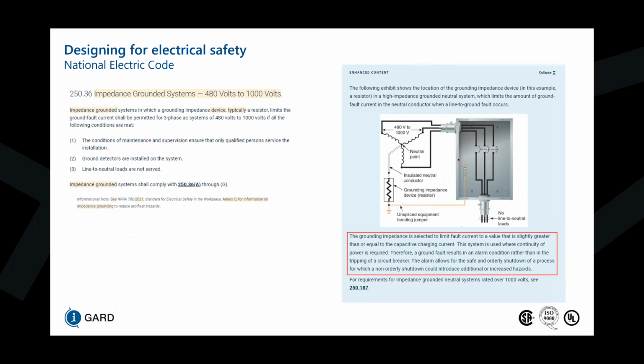Now, if we look at the National Electrical Code in 250.36, it allows impedance grounding systems to be used as long as line to neutral loads are not served. And basically, the grounding impedance is selected to limit fault current to a value that is slightly greater than or equal to the capacitive charging current. Therefore, any ground fault that results is not going to cause transient overvoltages in the system because we're sizing in accordance to the charging current. And that will allow you to continue operating until you have a downtime where you can address the phase to ground fault that's existing in your system.